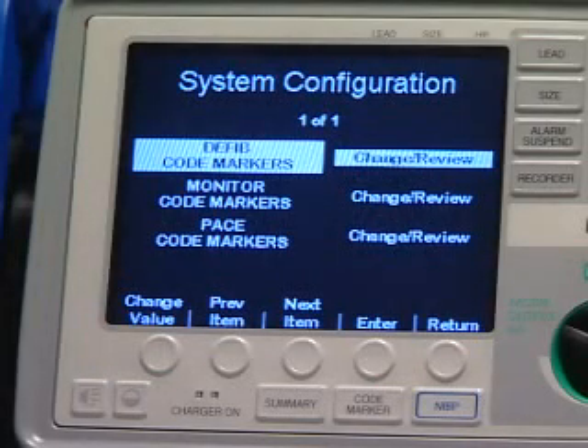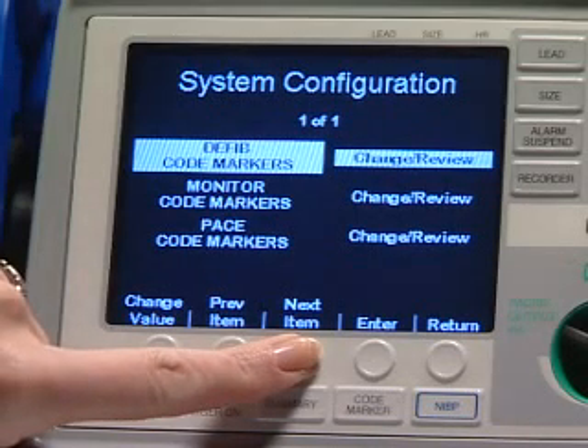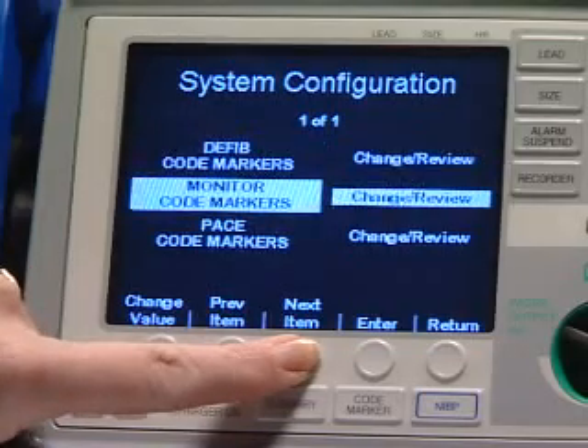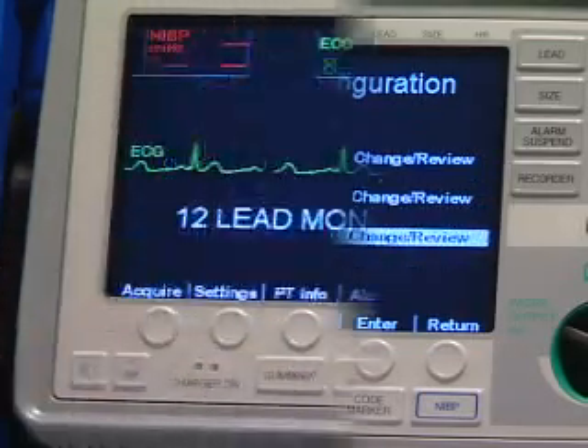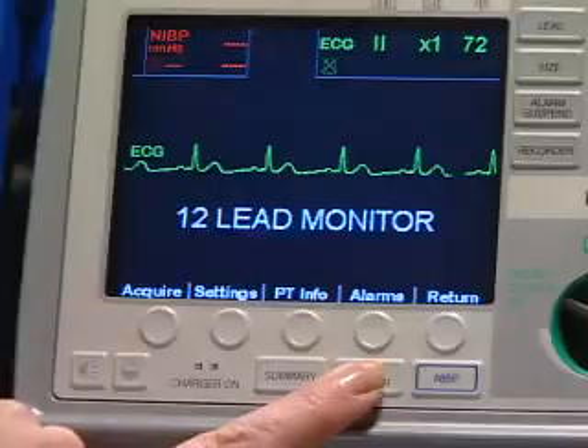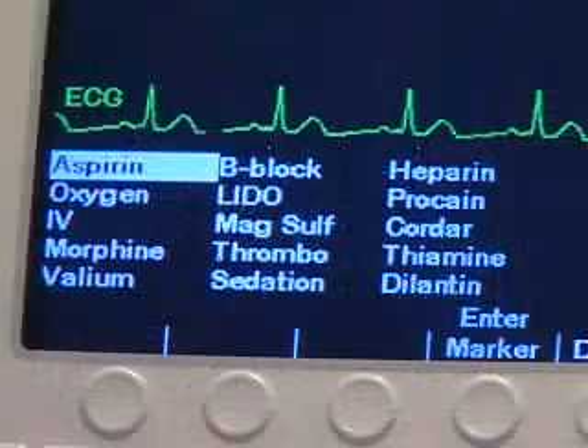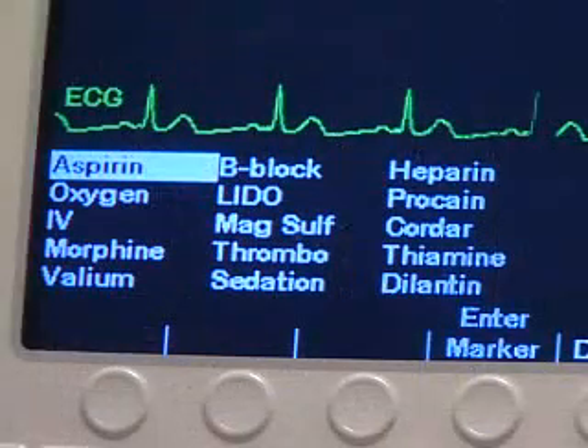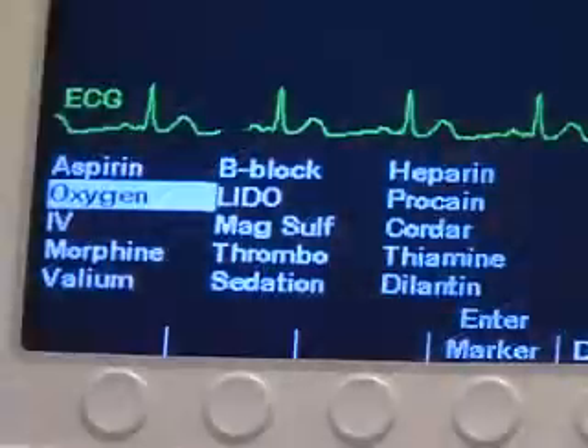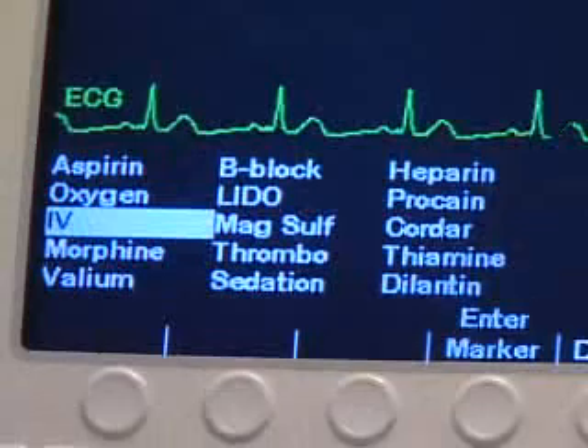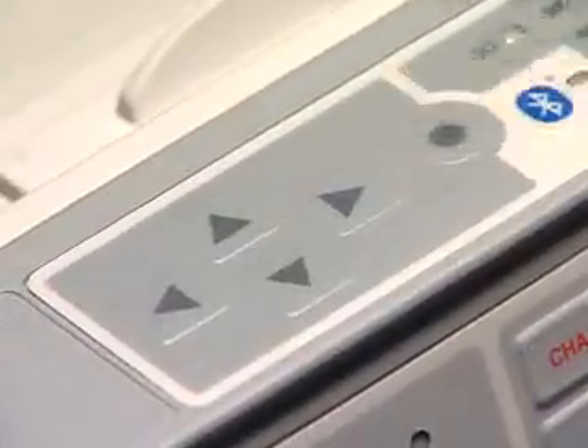Protocol Assist code markers can be configured to the specific protocols of your EMS agency. Separate code marker lists are available for defib, monitor, and pace modes. When you press the code marker button on the front panel of the E-Series, the unit displays a pre-configured list of clinical actions. The scroll keys on the top of the unit are used to scroll through the available markers. To record the intervention, press the Commit key on the top of the E-Series or the Enter soft key.